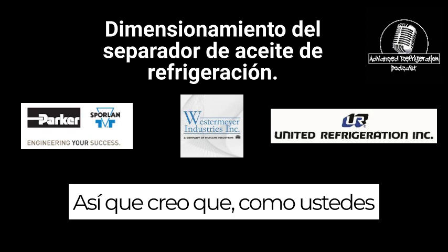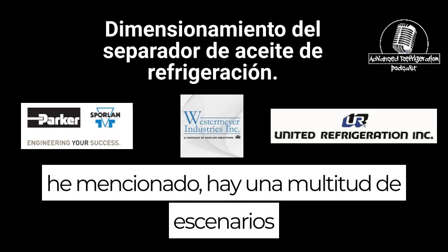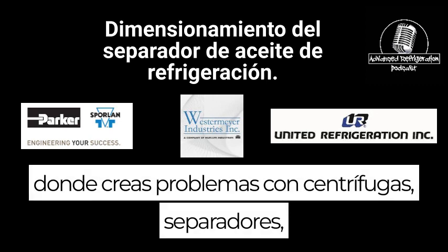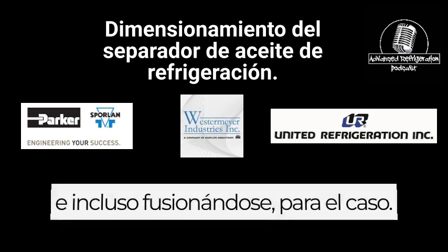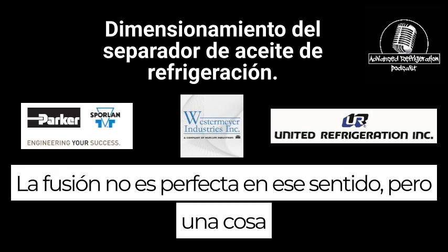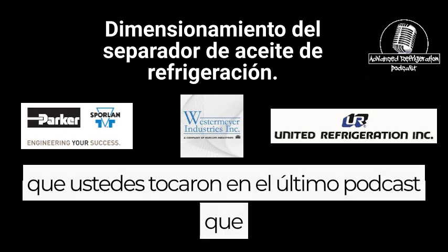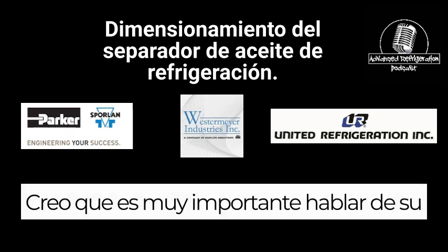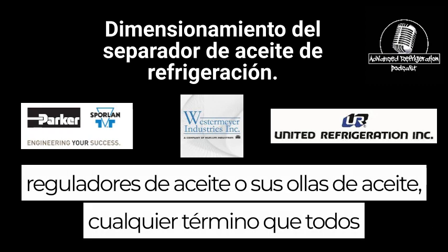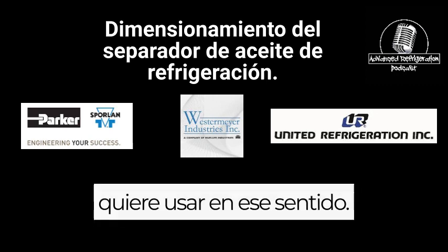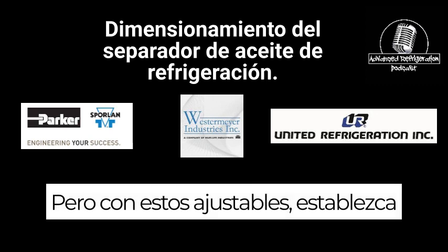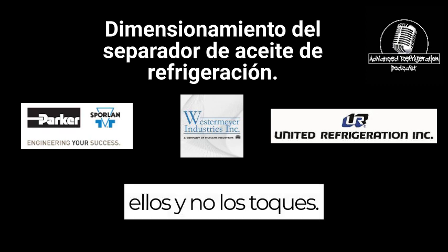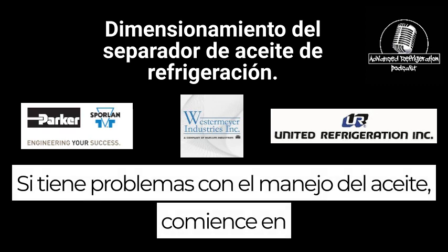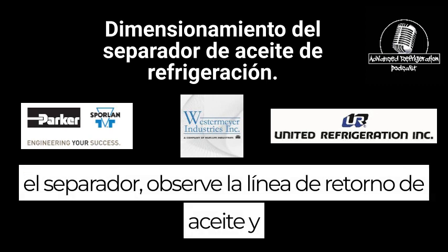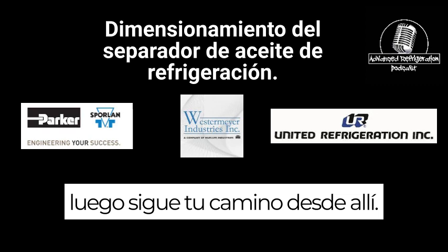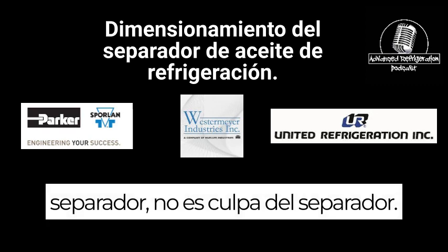So I think, as you guys have mentioned, there's a multitude of scenarios where you create problems with centrifugal separators, and even coalescing for that matter. Coalescing isn't flawless in that sense. But one thing you guys touched on in the last podcast that I think is so important is talking about your oil regulators or your oil pots, whatever term everybody wants to use. With these adjustables, set them and don't touch them. If you've got oil management problems, start at the separator, watch your oil return line, and then work your way from there. Because if oil is leaving that separator, it's not the separator's fault.